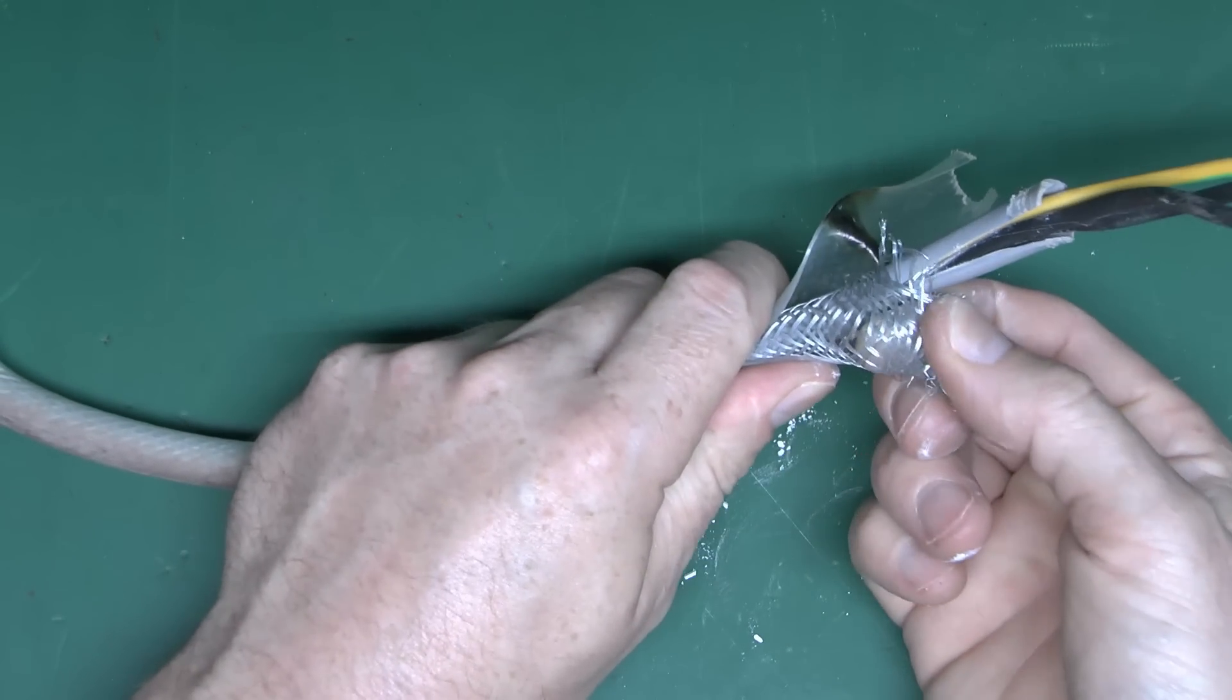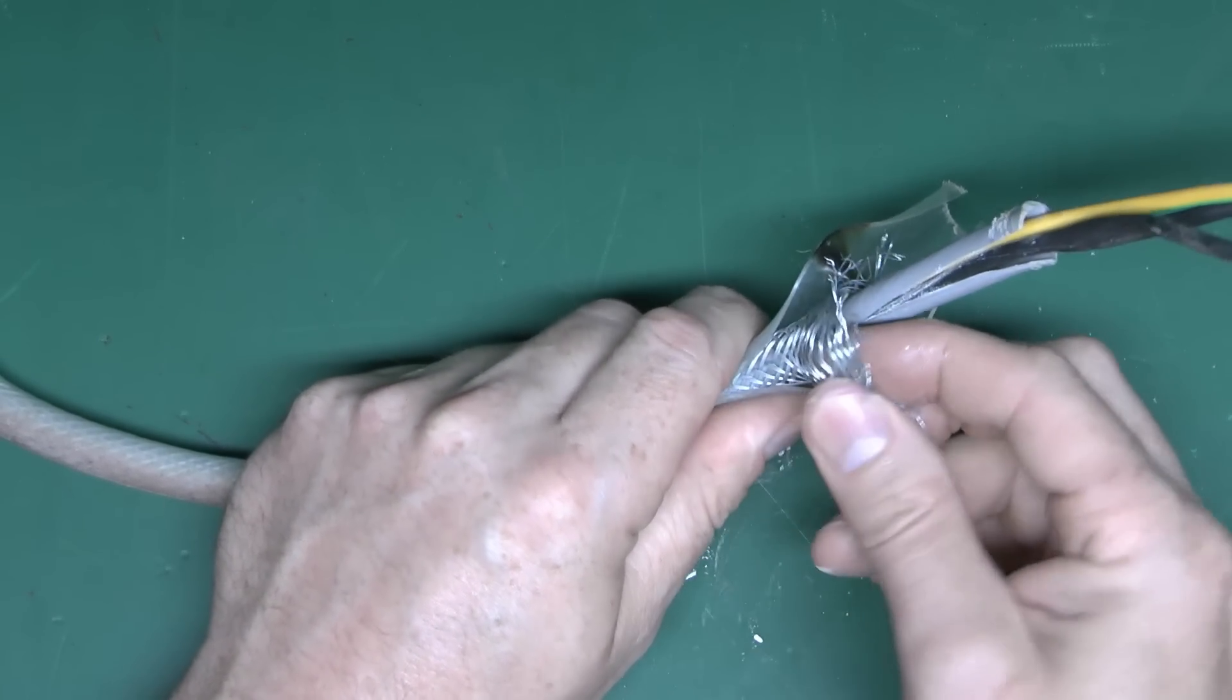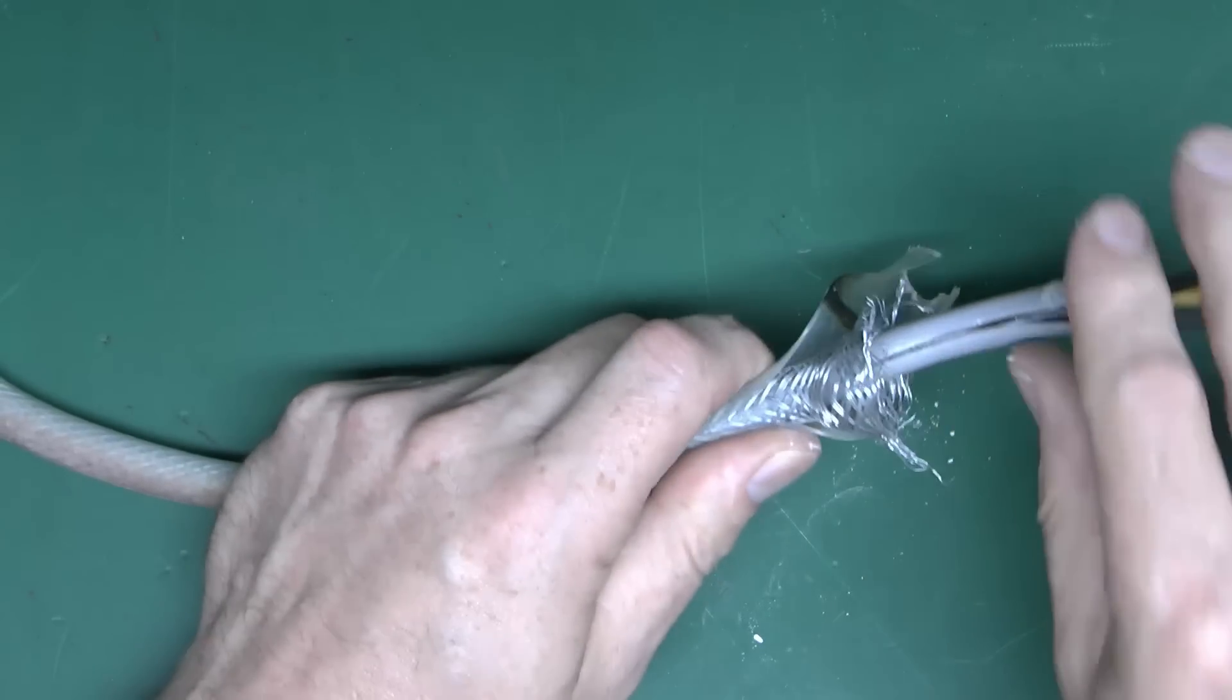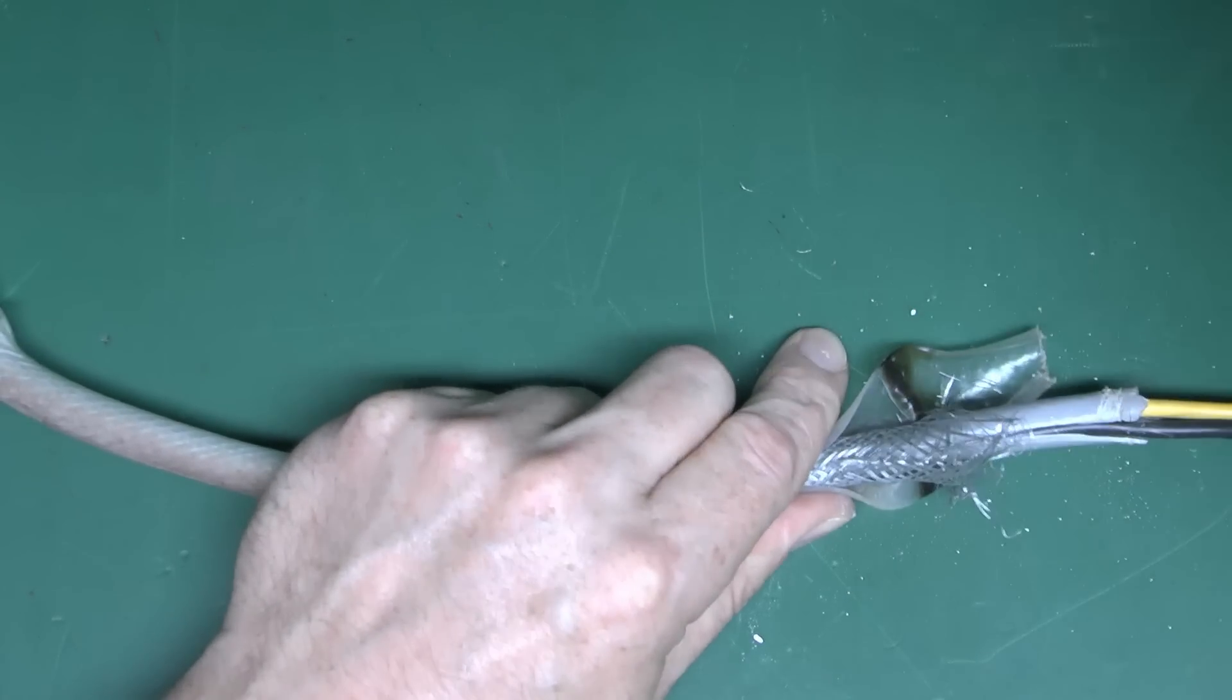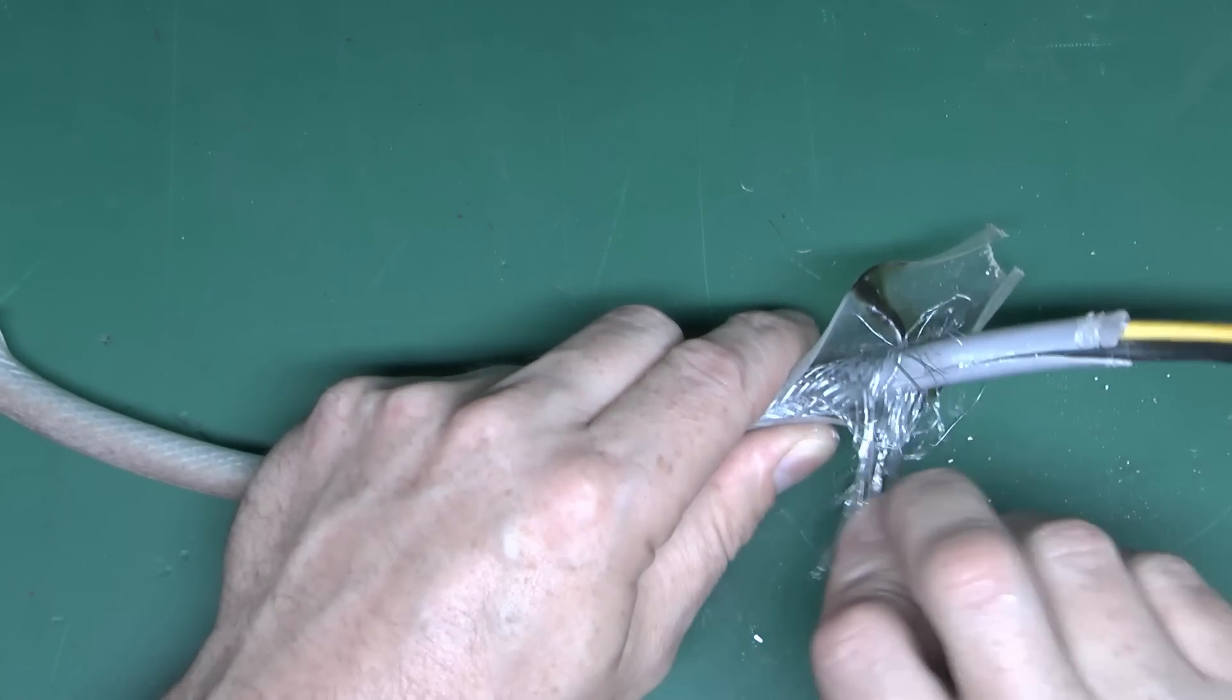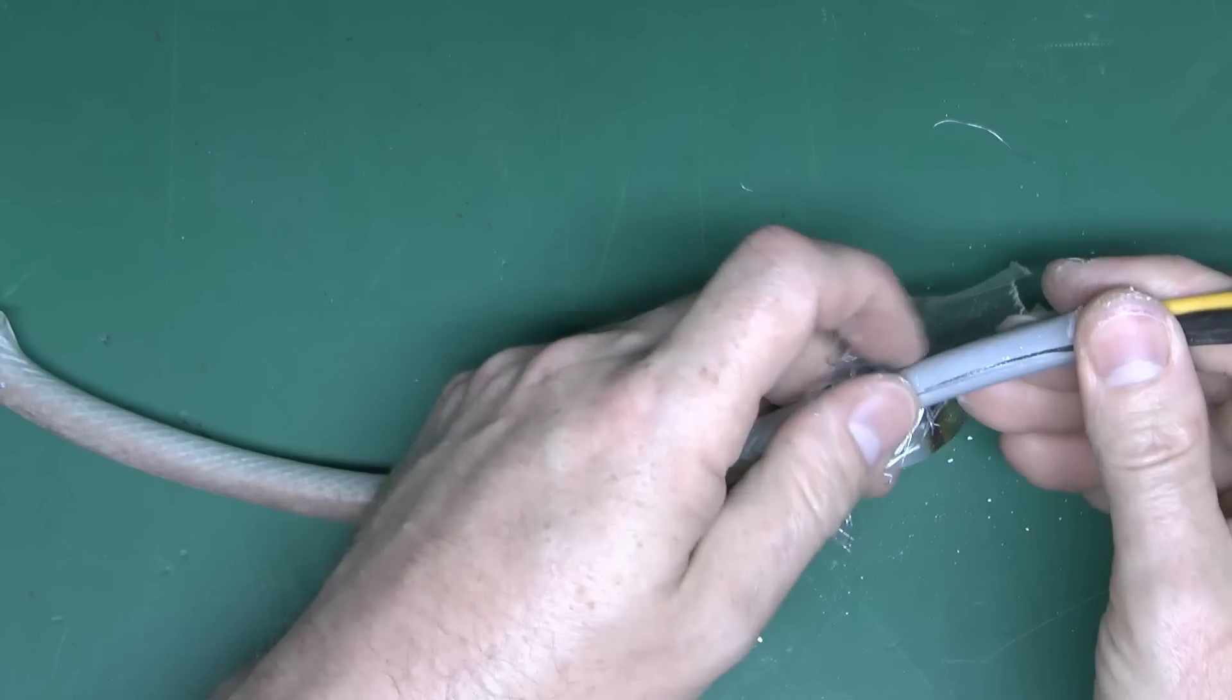This is not going to provide any mechanical protection, because it's very thin, as you can see, and it's very soft, and it's quite easy to cut through as well. I'm going to just take the knife here, and pretty much slice straight through most of that. So certainly not something that's going to be durable and suitable for use underground.